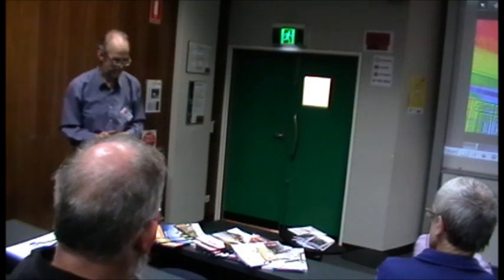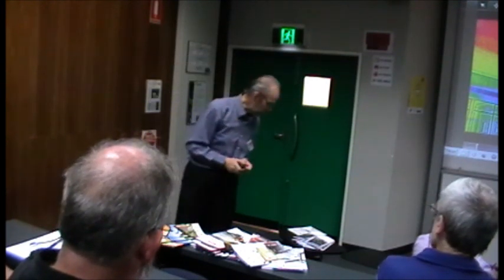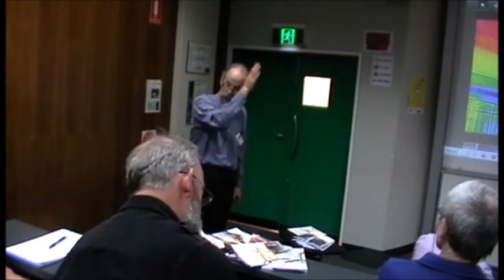Low E glass, normal glass, you said you've got 0.85. Low E coatings, what do they change it to? Right, when they talk about low E glass, one of the things we've got to understand is that they're talking about the emissivity over a bigger range than just what we're looking at with our cameras. When we're talking about these emissivity figures, they apply to the range we're looking at, the 8 to 14 micron range. Emissivity varies according to the wavelength. And a lot of that low E glass has low emissivities at the shorter wavelengths, where the sun has the maximum heating effect.